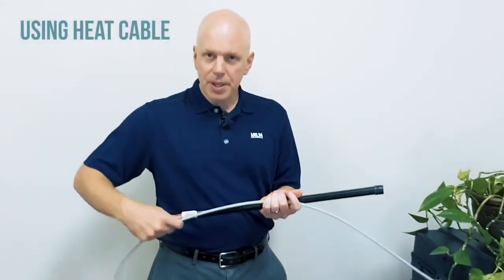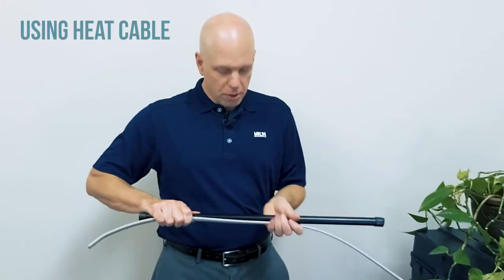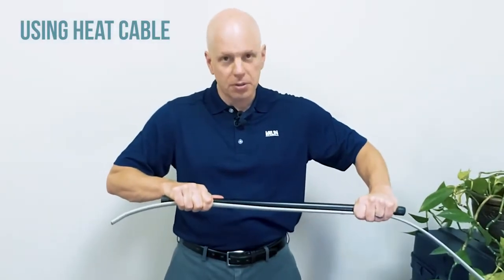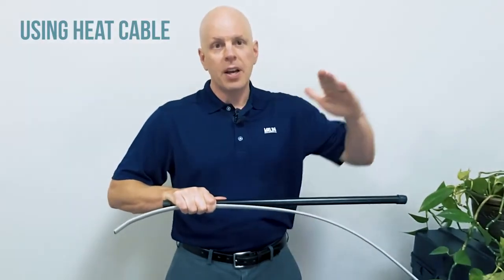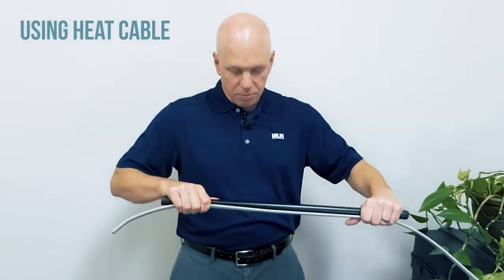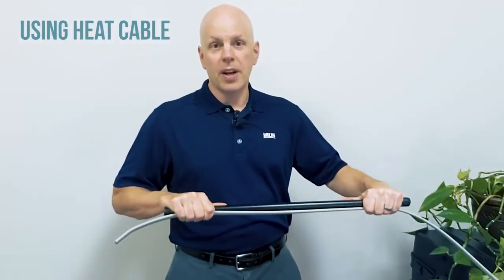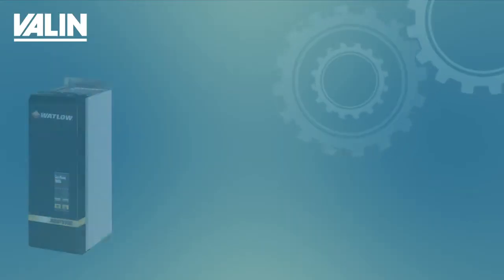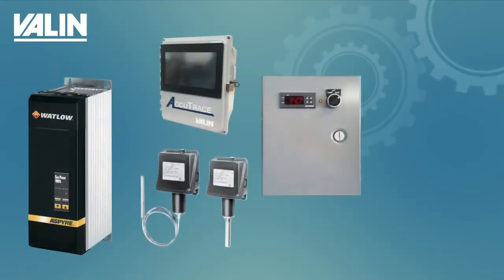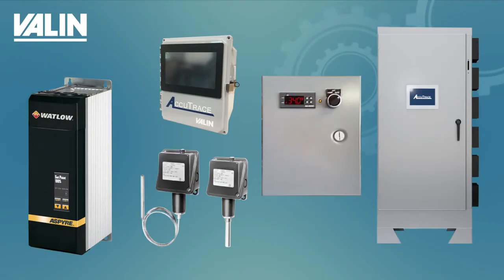Having said that, you don't typically wrap heat cable around a pipe. You would rather install it like this, parallel to the pipe, either in the 5 or 7 o'clock position. If properly sized, that's going to provide sufficient heat to maintain your temperature in your application. As with heat tape, you always want a thermostat or control panel in your system. Also, the NEC requires all heat trace be controlled by a ground fault equipment protection breaker.